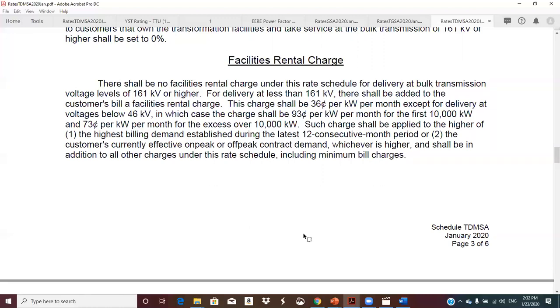Or the customer's currently effective on-peak or off-peak contract demand. You rarely, if ever, see people actually exceeding their contract demand because there are penalties in that. But let's say your contract is 5,000, and you actually pulled 5,200 one month, two months ago—they say, well, forget the contract, they're going to find the biggest one. If the contract's 5,250 and you bill 5,200... no wait, if the contract's 5,200 and you bill 5,250, they're going to remember that 5,250. You're going to pay for that 12 times, that extra 200.